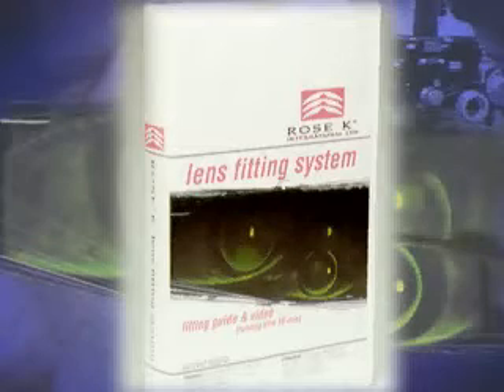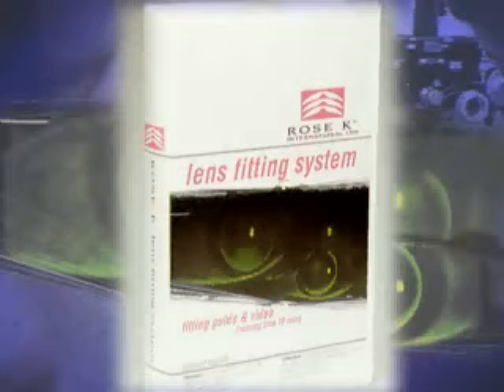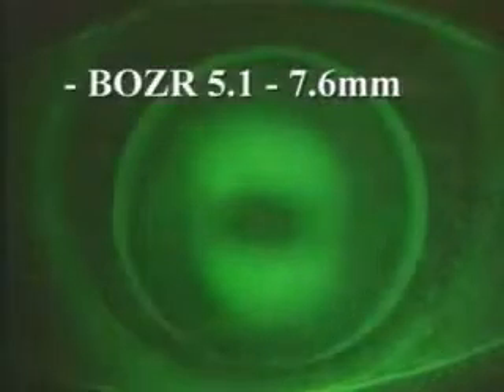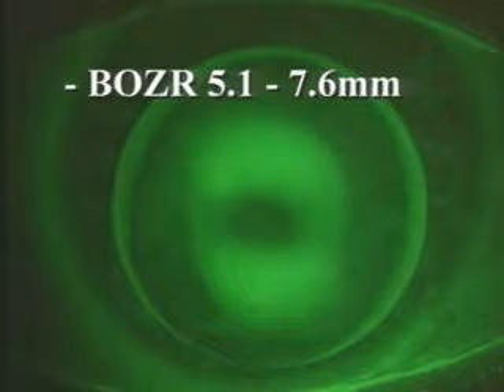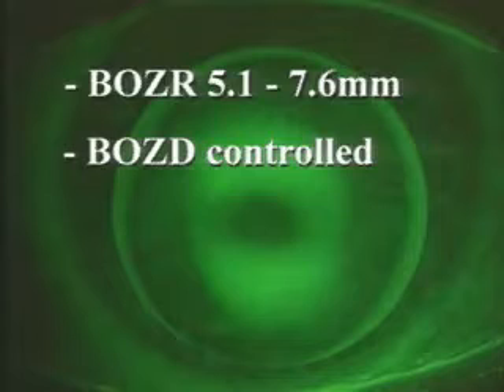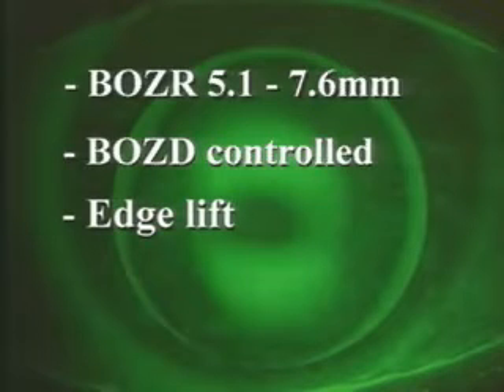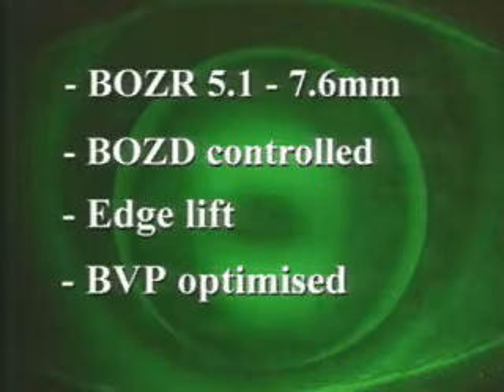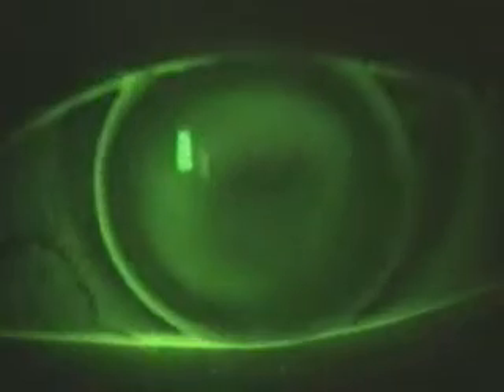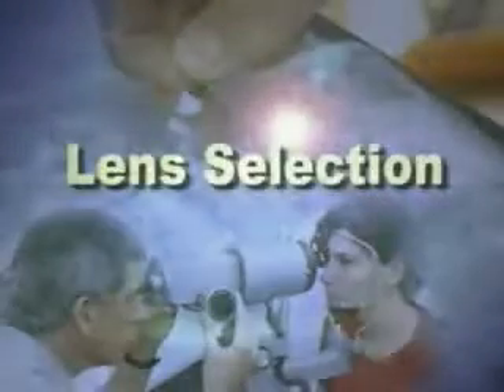The Rose K system is designed to achieve a high percentage of first-time successful fittings at any stage in the progression of the disease. There are a number of key design features in the Rose K system. These include an extensive range of back optic zone radii, smaller back optic zone diameters as the radius steepens, simplified edge lift control to facilitate ordering, and significantly increased lens power as the radius decreases when fitting advanced cases. These unique design features guarantee a high success rate when fitting the potentially difficult keratoconic patient.